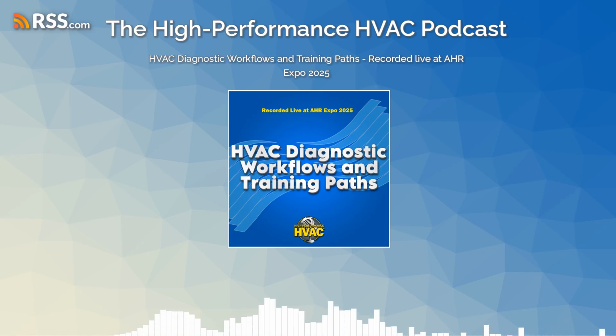Right. Yeah. Well, I don't know if it's a misconception about static pressure, but it's counterintuitive. Because you think that if you have a major blockage in a system, your pressure is going to go up. But in reality, your fan, especially a PSC motor, can't move the air, and your pressure actually goes down. So it's kind of counterintuitive. Yeah. So unless you're looking at both, you can be easily tricked into thinking it's something, but it's actually something else.